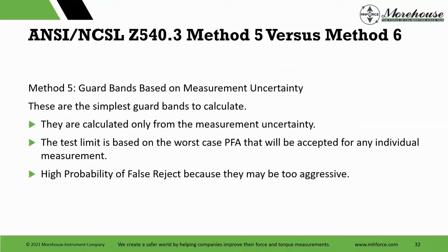So I use terms such as method 5 versus method 6. Now, the ANSI Z540.3 handbook has about 6 decision rules in it, 1 through 6. 5 and 6 are the easiest to implement. Method 2 is fairly easy to implement, and then others require you to have a lot of history of the devices, so they're more difficult to implement. And then ISO 17025 doesn't really give us the guidance other than agreed upon decision rules. So you can make up your own decision rule, really. But that's hard to do. Go ask a lab to do that. Someone's going to need to custom program something, and that's never cheap.